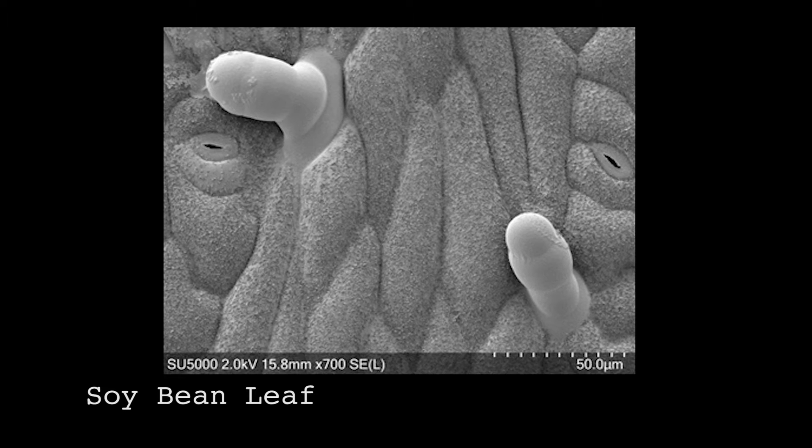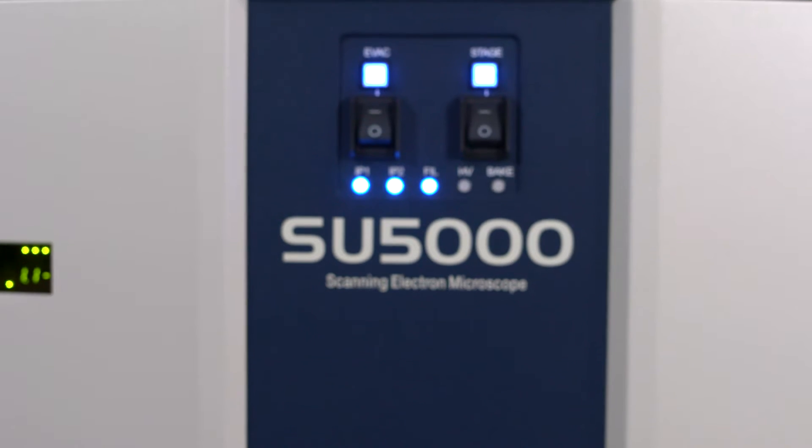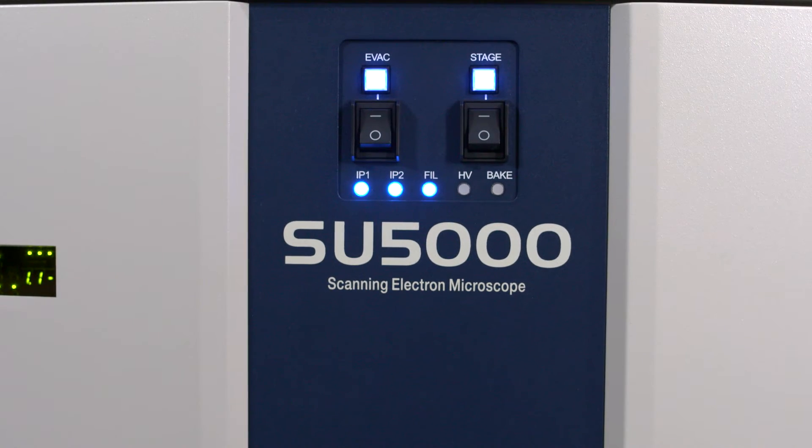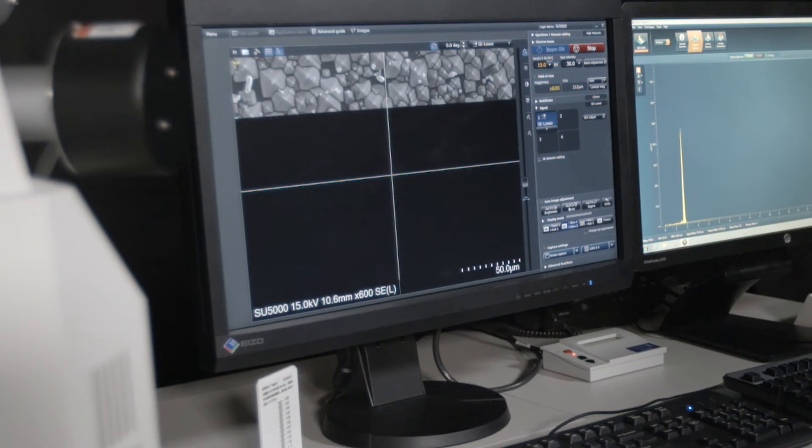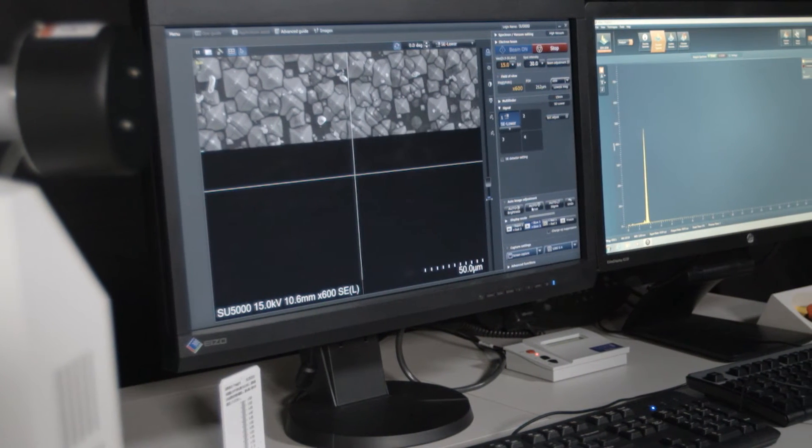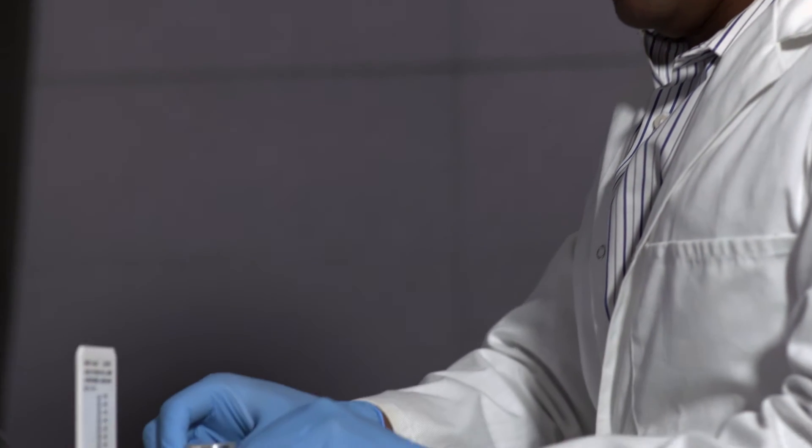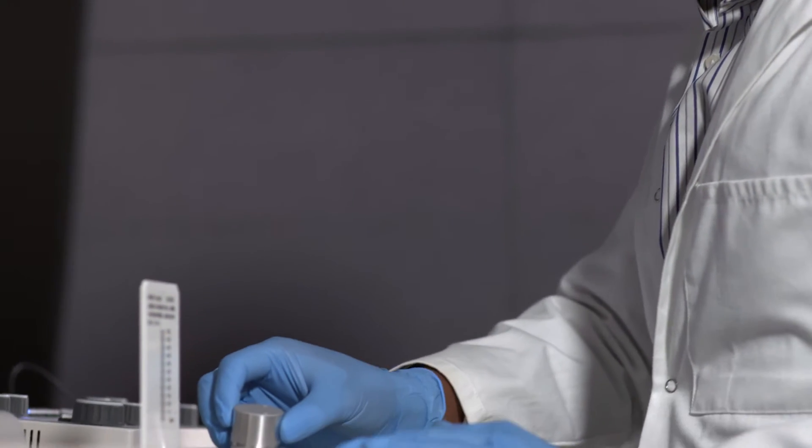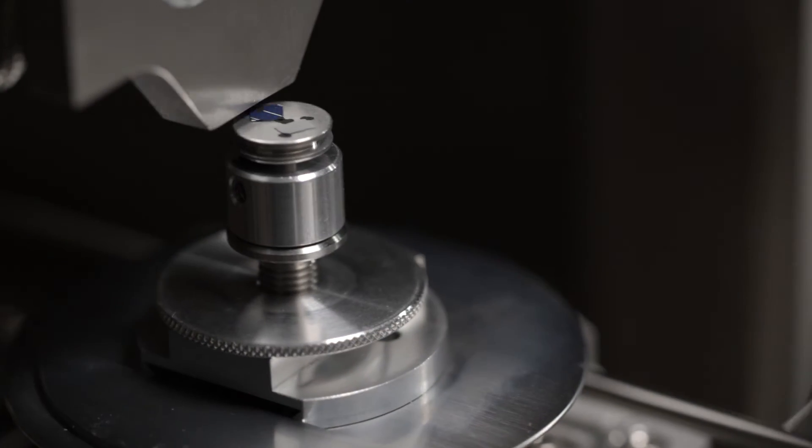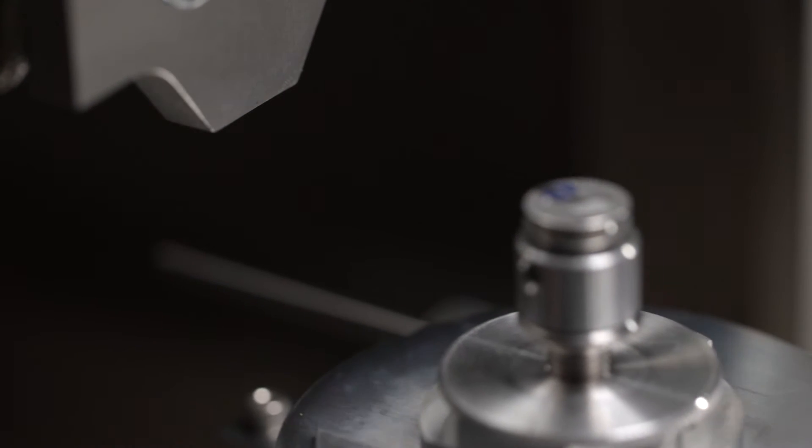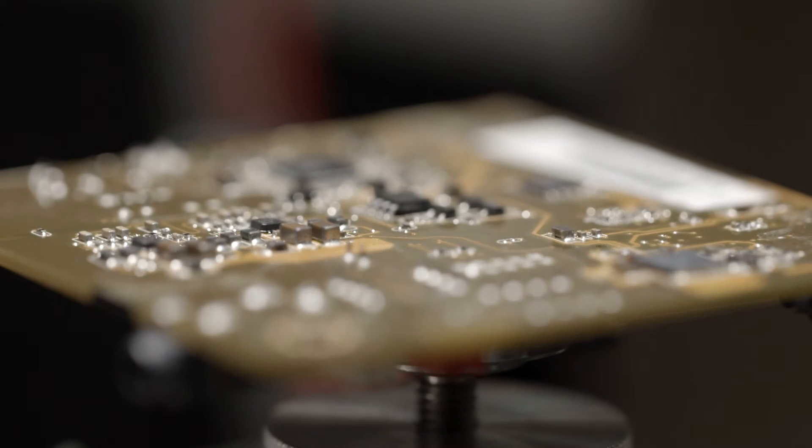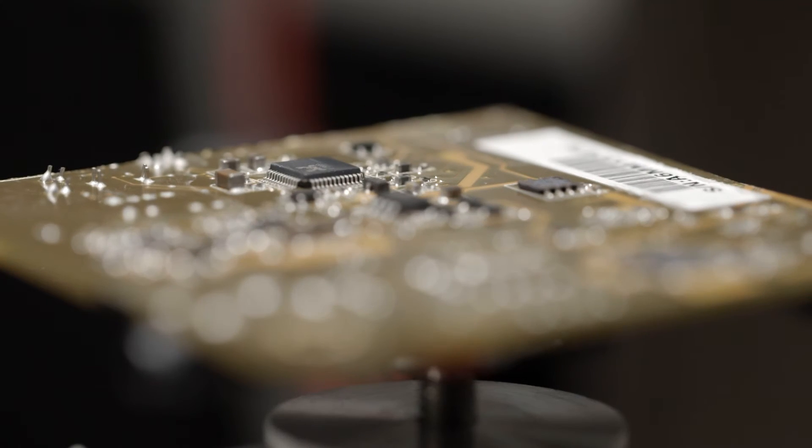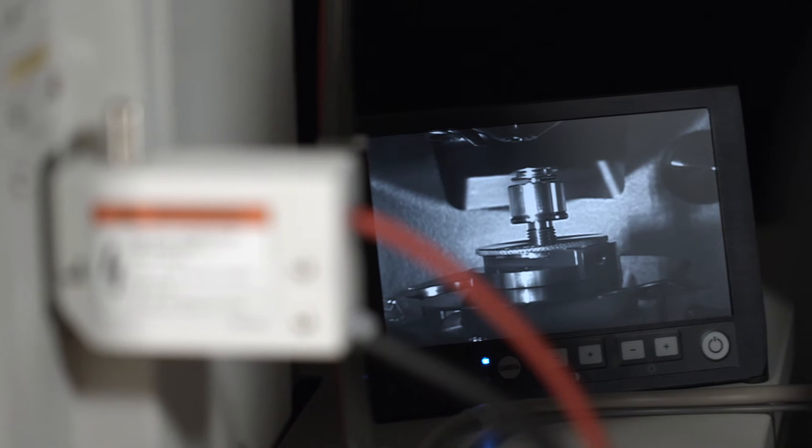The Hitachi SU-5000 VP-FE SEM is equipped with three high angle takeoff ports for chemical analysis, EDS, and/or WDS, yielding an analytical working distance of only 10 millimeters. The chamber itself is designed with an additional port for an EBSP detector, and all these analytical capabilities offer simultaneous direct line of sight to the sample, providing unparalleled sample analysis with 11 ports in all.